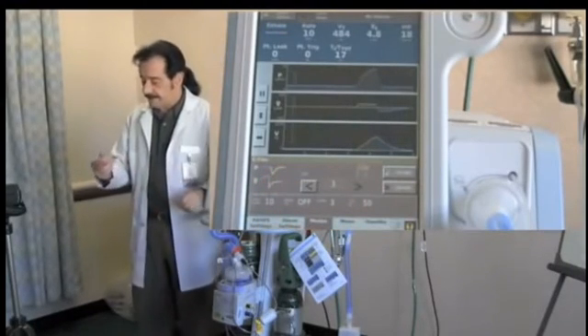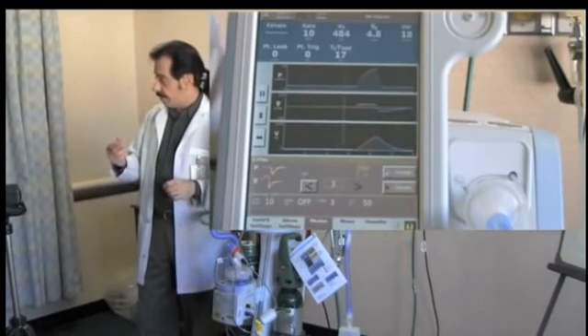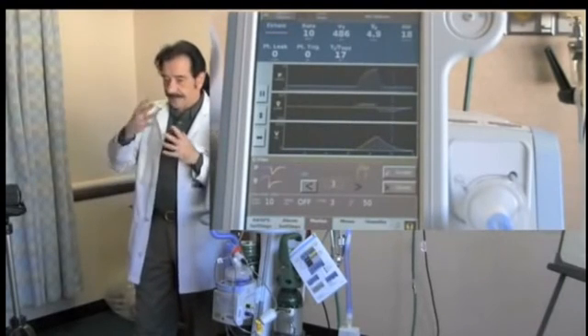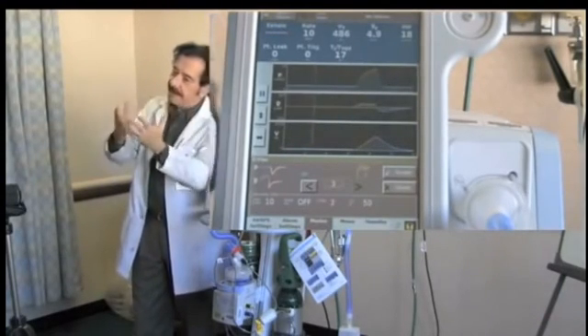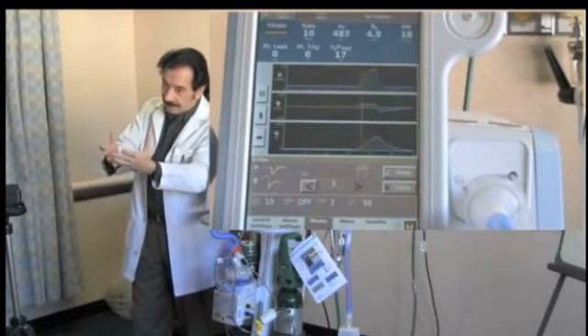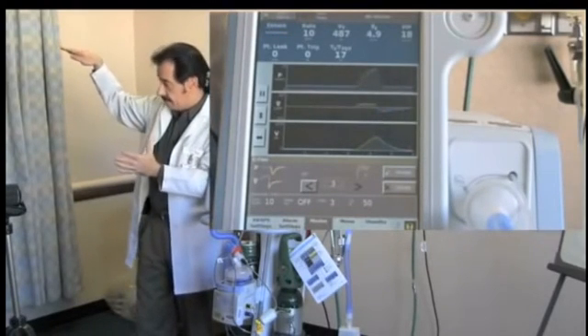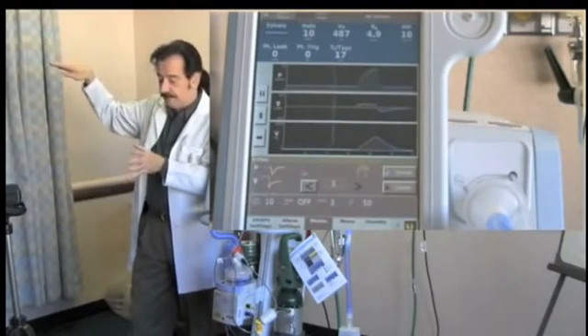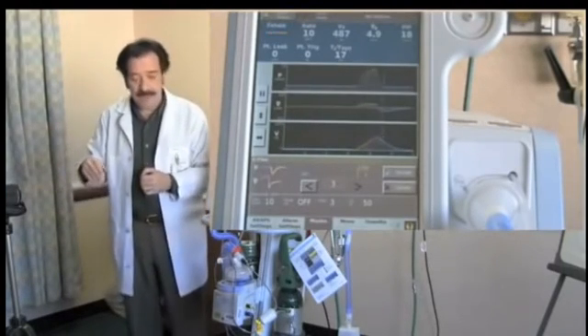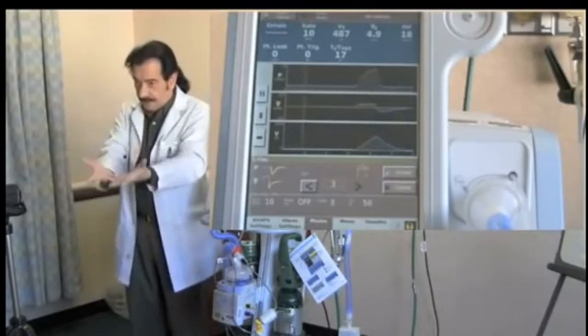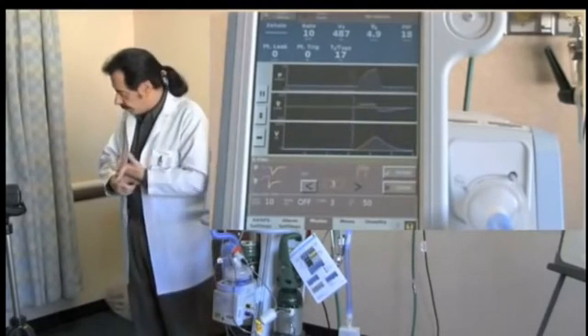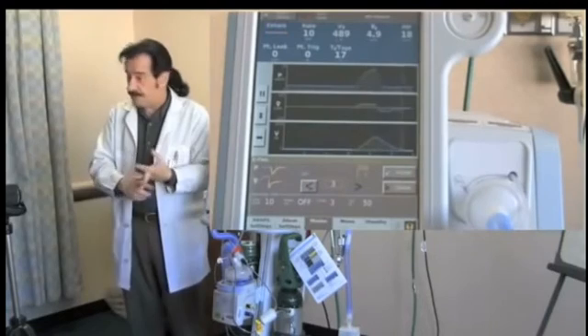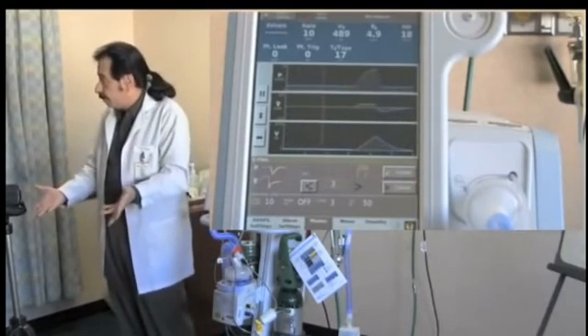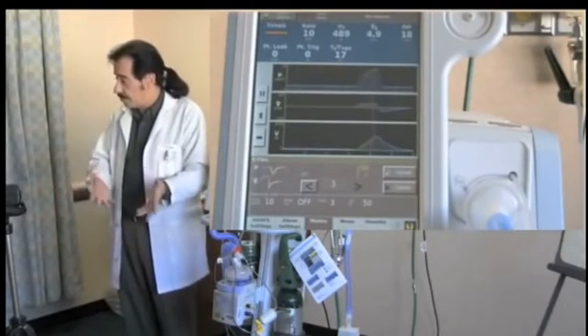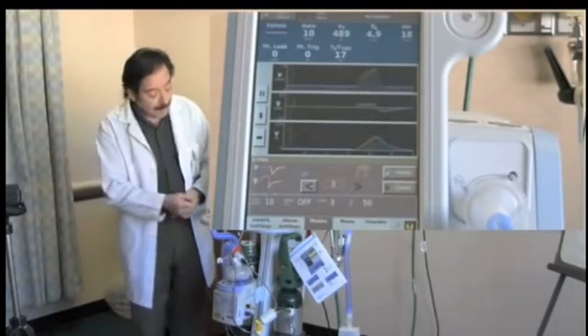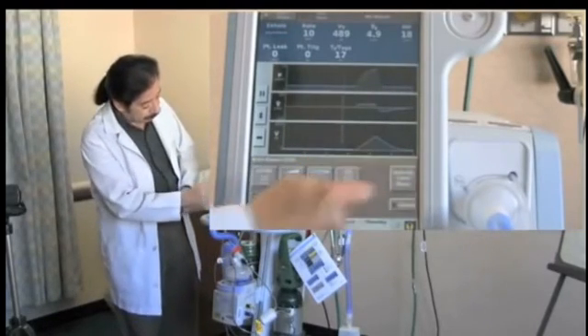What the C-Flex does is it takes the foot off the accelerator at the start of exhalation. So it eases out that flow so that the patient can begin to get their expiration flow out, and then by the end of exhalation have attained its CPAP pressure. Okay, so there's never a big drop in circuit pressure. It just makes it easier for them to begin their breath out. Okay, so what kind of patient should I use this on, and what setting should I use? I don't know. You just have to play it by ear or adjust it for each patient to their comfort. Okay, but it's there for you, and it's a good mode.